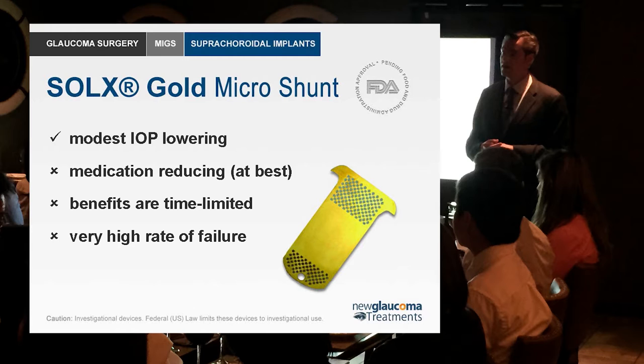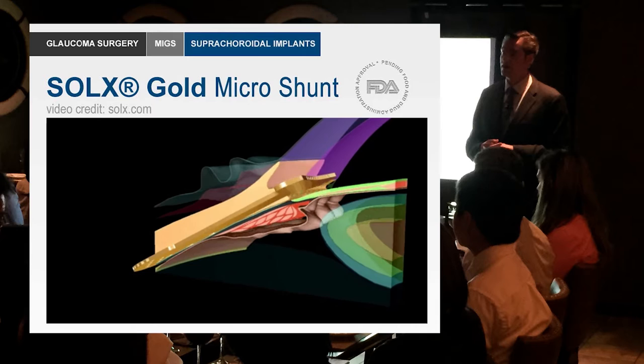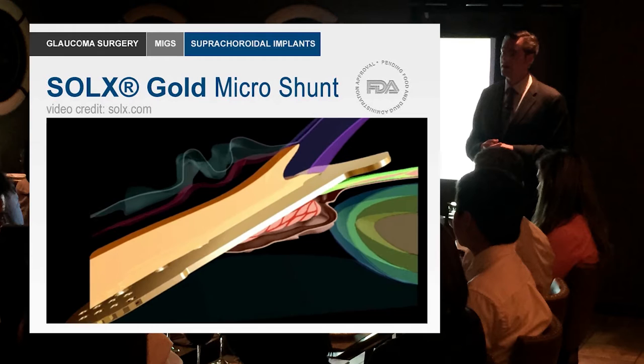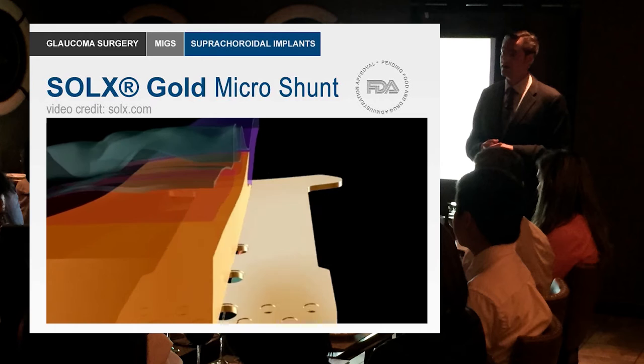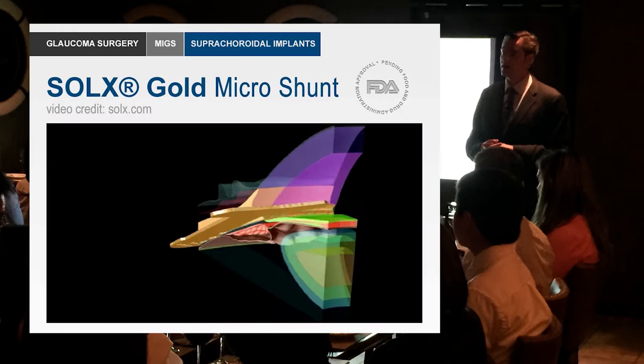One of the earliest suprachoroidal implants is the SOLX gold micro shunt. The design involves two thin gold plates sandwiched together with little channels in between them. The idea was that the body shouldn't react to gold since it's pretty inert, and the shunt would be placed in the angle in the suprachoroidal space, allowing fluid to come in and flow out through these little pores and channels.